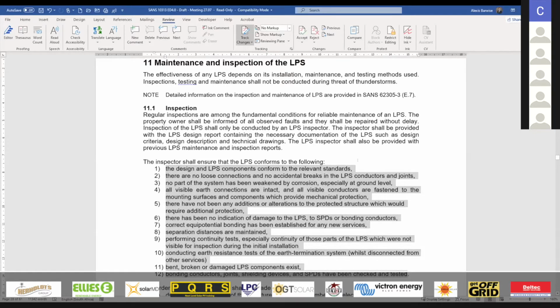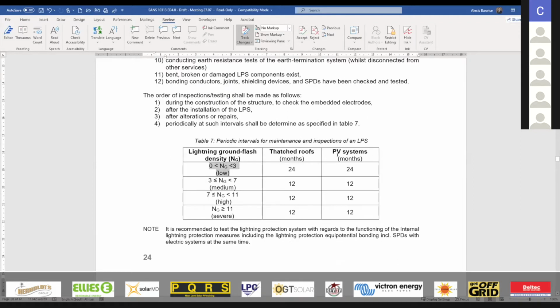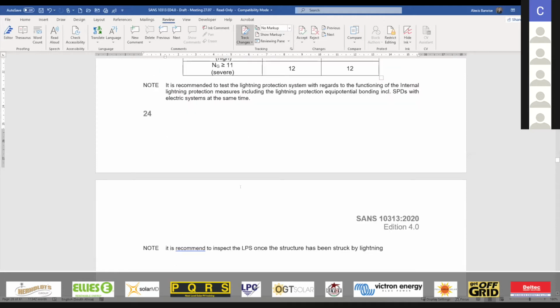And here you can see again a guideline. Depending on the lightning ground flash density, the months would vary in terms of when a maintenance test should occur. So for areas below 3, every 2 years would be acceptable, and for areas above 3, we would have a lightning maintenance test certification done every year.